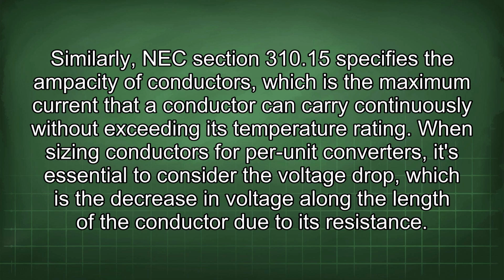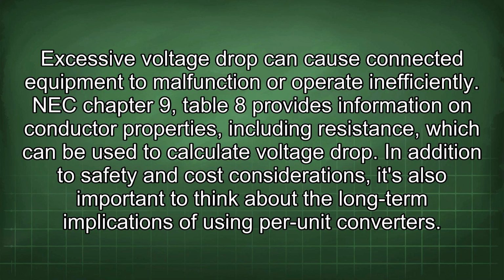When sizing conductors for per unit converters, it's essential to consider the voltage drop, which is the decrease in voltage along the length of the conductor due to its resistance. Excessive voltage drop can cause connected equipment to malfunction or operate inefficiently. NEC Chapter 9, Table 8 provides information on conductor properties, including resistance, which can be used to calculate voltage drop.